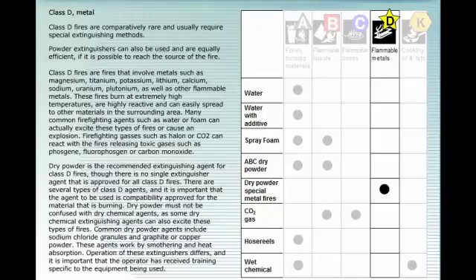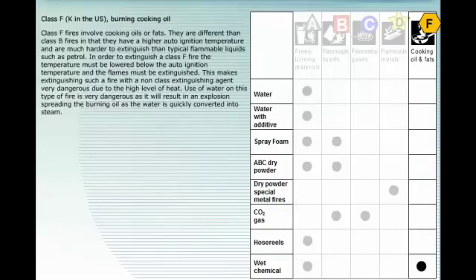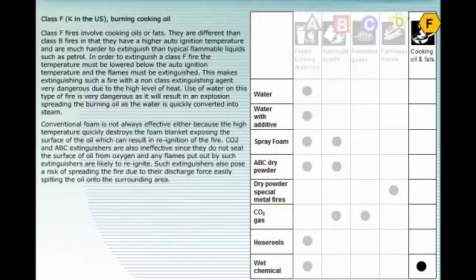Class F fires involve cooking oils or fats. They are different than Class B fires in that they have a higher auto-ignition temperature and are much harder to extinguish than typical flammable liquids such as petrol. In order to extinguish a Class F fire, the temperature must be lowered below the auto-ignition temperature and the flames must be extinguished. This makes extinguishing such a fire with a non-class extinguishing agent very dangerous due to the high level of heat. Use of water on this type of fire is very dangerous, as it will result in an explosion spreading the burning oil as the water is quickly converted into steam. Conventional foam is not always effective either because the high temperature quickly destroys the foam blanket exposing the surface of the oil, which can result in re-ignition of the fire.